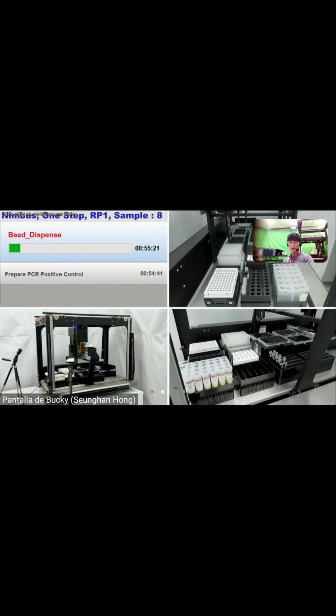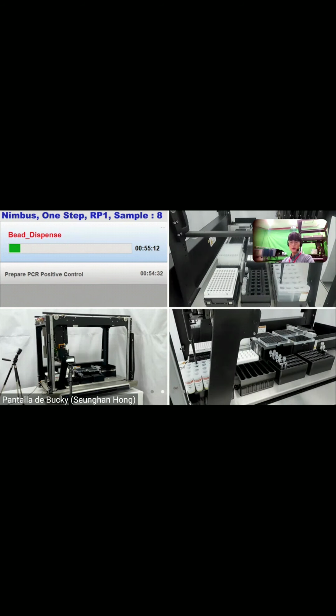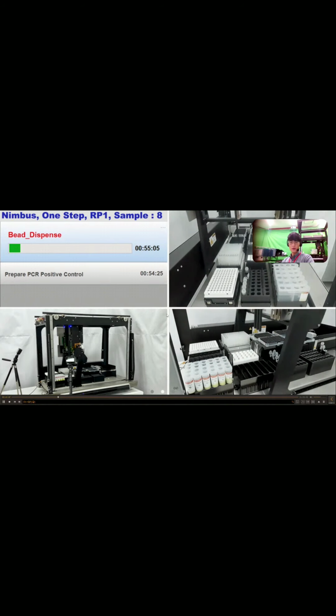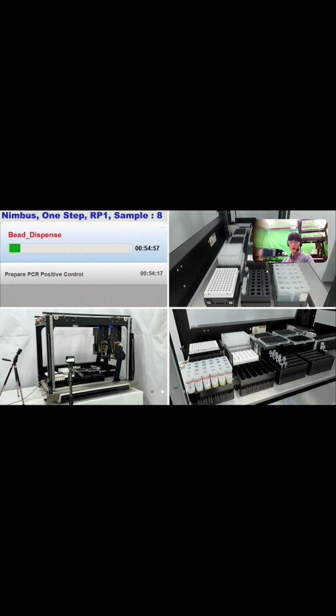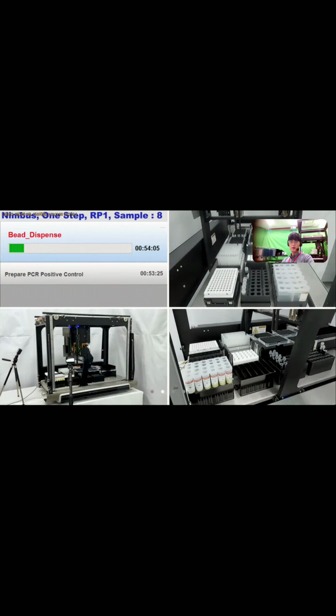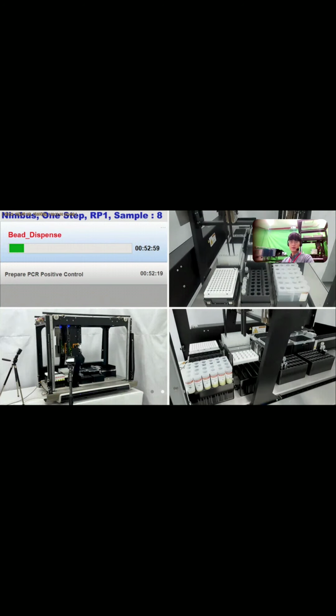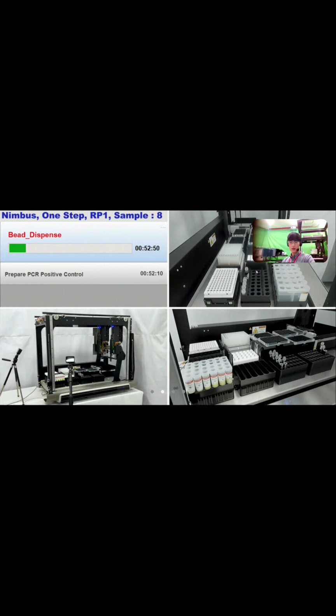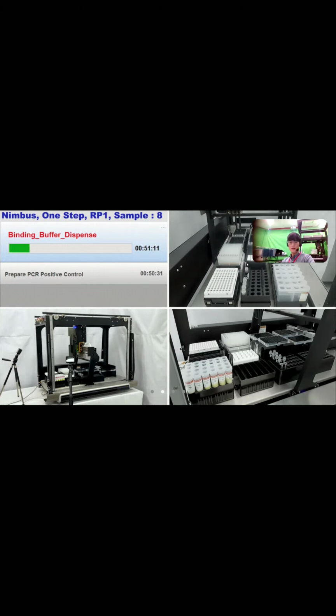And it is time to bead dispense. Even if the step is bead, the machine aspirates the binding buffer. When I made the video, I used the real binding buffer. Anyway, the binding buffer is dispensed at the G12 position, and the machine really aspirates the beads, does some mixing, and mixes the beads and the binding buffer at G12. They're gonna do some mixing stage. Yeah, dispensed. At this moment, the engineer has to check the color is changed, right? Color change means the bead dispense is done correctly.